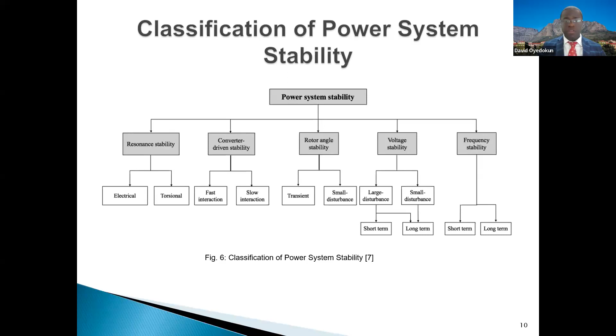When there's an event in the power system, I usually like identifying what is the root cause, and then the reaction to it, so there's a reaction to an action. Let's assume the action is we lose one unit at one of our generating stations. At that instant, the next millisecond, the load is slightly higher than generation, and that typically drops the frequency.